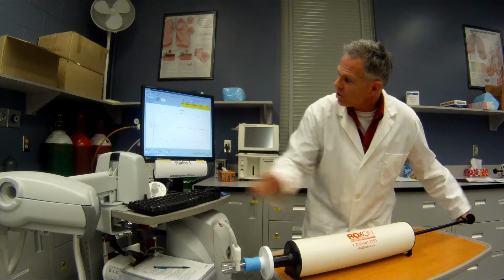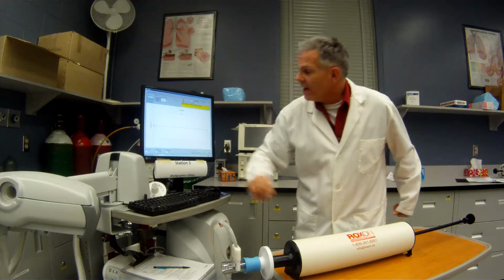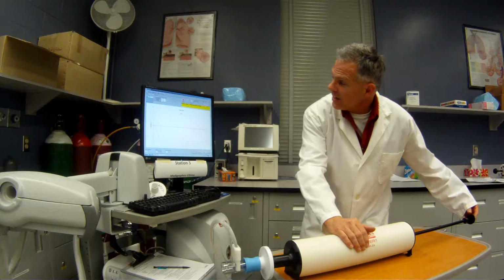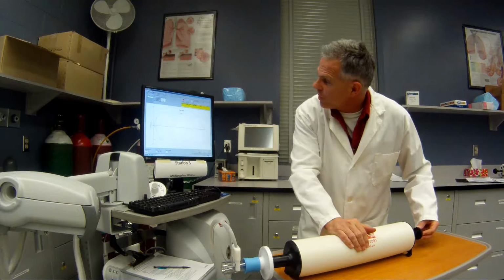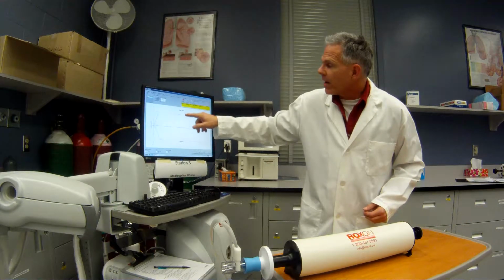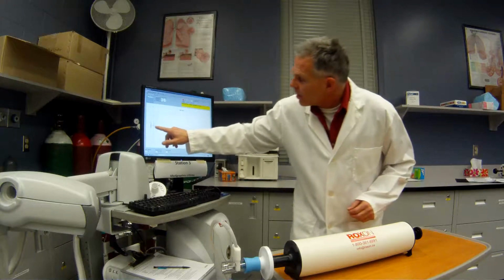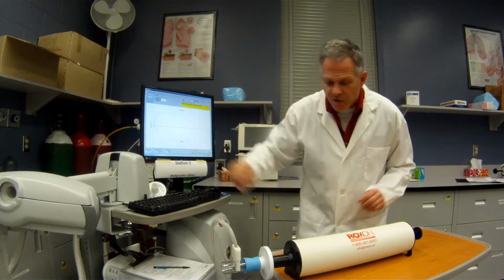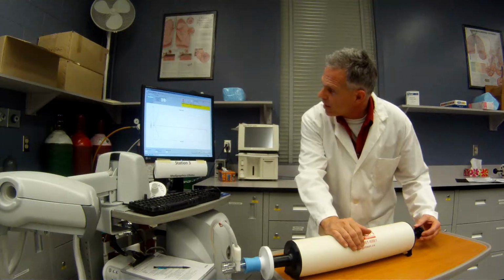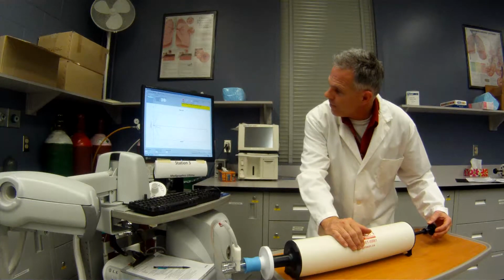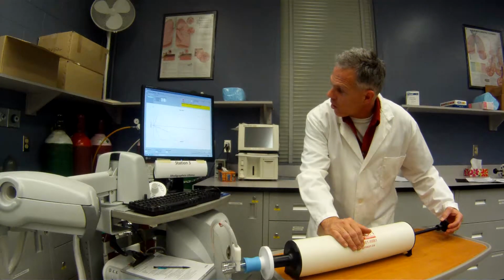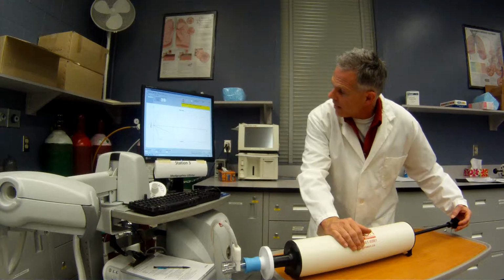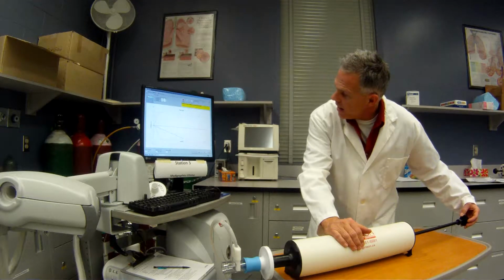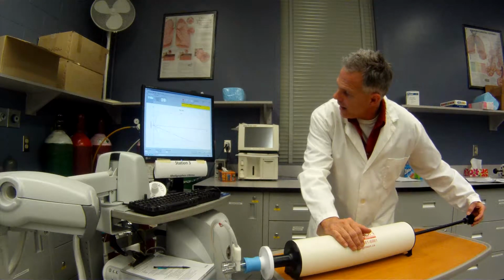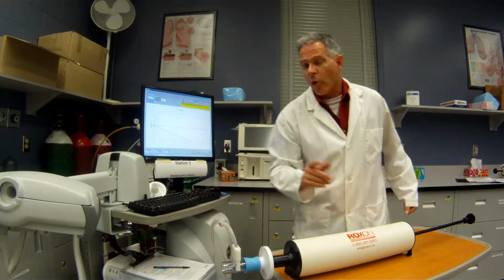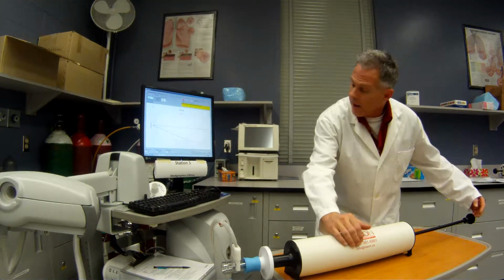All right, so you can see I've got a little line down here telling me that it's measuring 3 liters. This has been working quite well, and then it tells me to inject air and now withdraw air. Now, the goal is to do this on a wide variety of flow rates. So I'm going to do a really slow one here. So for our ATS criteria, we have to do both high, slow, and low flow rates. So I'm going to do another low flow.